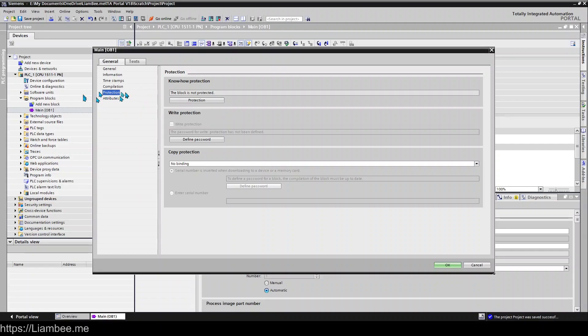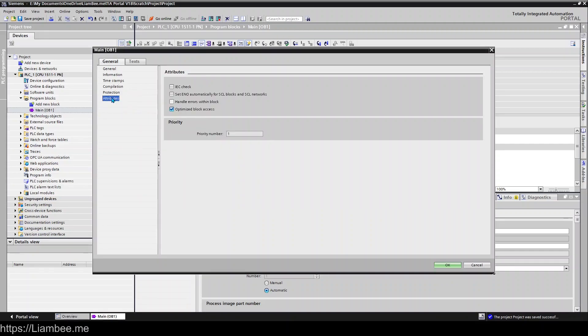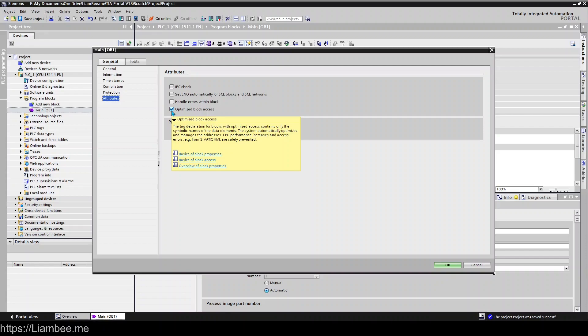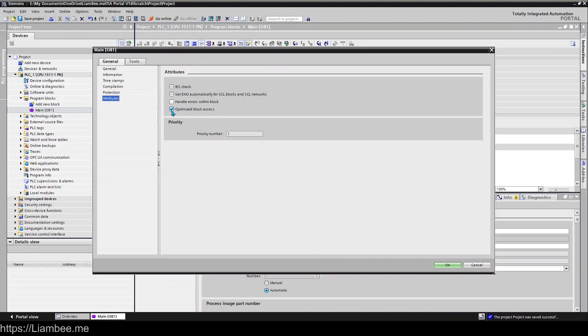And then Attributes. This is where you will most likely come in to change stuff. So the biggest one will be this one here, whether you are Optimized or Unoptimized. And in the video description I will link an article that I wrote about the difference between Optimized and Unoptimized data. Personally I don't use Optimized. I uncheck every single block that I create and that's because I make use of particular instructions that need to explicitly know where their data is. So Optimized, you don't necessarily know where your data is. TIA Portal optimizes it and puts it or packs it slightly differently for the block to optimize its space in the controller.